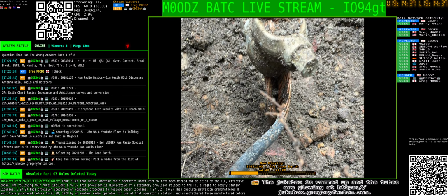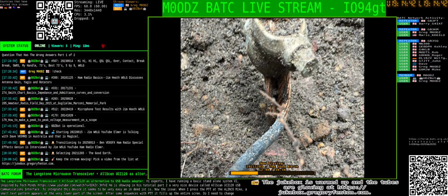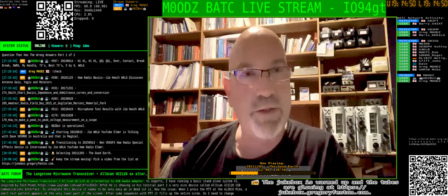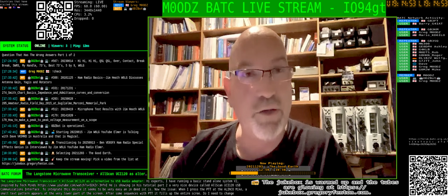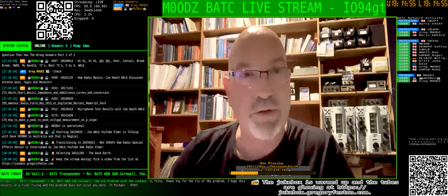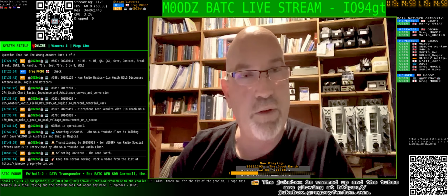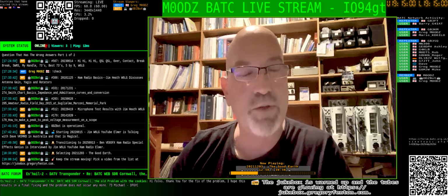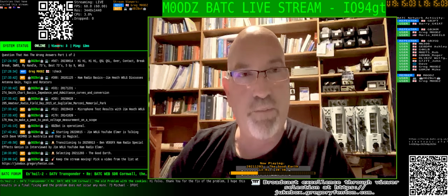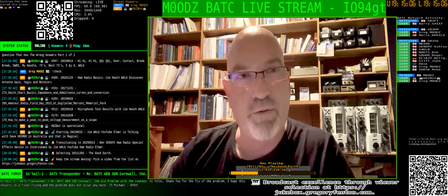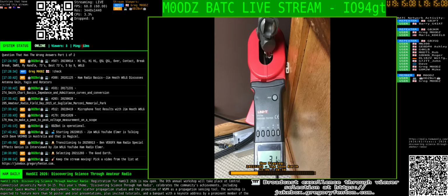I won't use a copper plated steel rod. I use copper water piping, class 2 water piping, for my earthing system. So the first thing is to determine what the resistance is. If you're fortunate and check it, you might find you actually have a very low ground rod resistance, let's say 5 ohms, which I'd say is the top limit for a radio station.